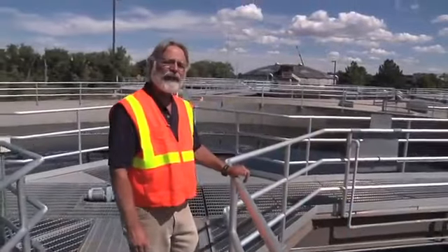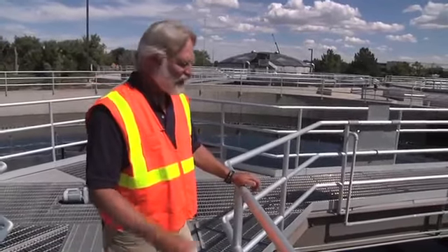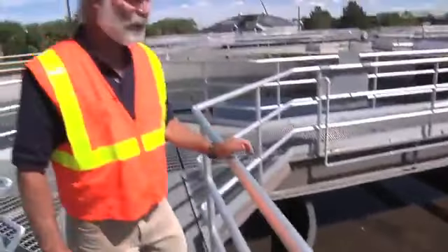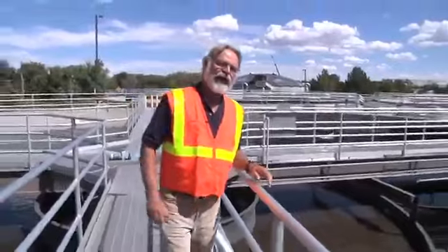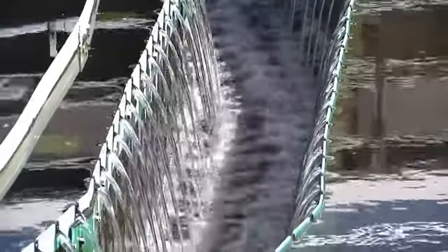The secondary clarifier is the last step in the secondary treatment process. In the secondary clarifier, our mixture of microorganisms and water comes into the center, and as you can see, we're forming nice floc particles that are starting to settle out. They flow down outside this ring and into the main part of the clarifier where the floc settles to the bottom and the clean water comes to the top and flows over the weirs on its way through our process.